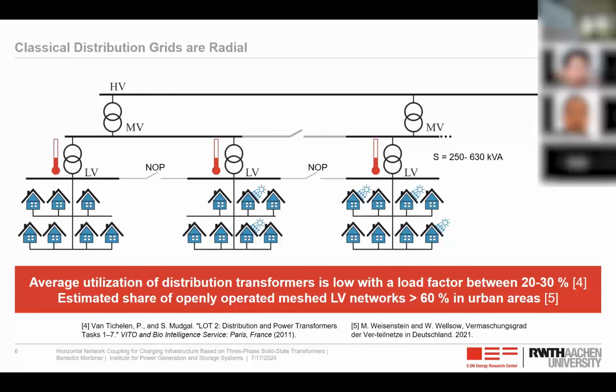And while our high voltage grids are typically meshed and n-1 operated, our classical distribution systems have a radial structure. And that means that we have a number of medium voltage transformers feeding different low voltage transformers, which typically just supply a single grid area. And the utilization of these distribution transformers is typically quite low, with a load factor between 20 and 30%.